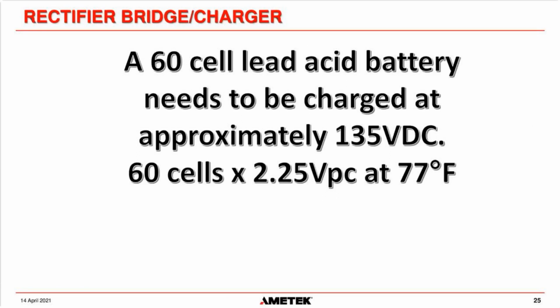That is really its only purpose, to keep your batteries charged. So if you lose power, your DC circuits will remain powered from the battery. And the thing about batteries is they are very sensitive to charge voltage. So a 60-cell lead acid battery needs to be charged at approximately 135 volts DC, which is 60 cells times 2.25 volts per cell at 77 degrees Fahrenheit. This is basically an approximate assumption. You have to look at your battery data sheet to make sure that the float voltage is what you think it should be. Some manufacturers like to see 2.23 volts per cell, some like to see 2.27 volts per cell, and sometimes they are quoted at 20 degrees Celsius. You've got to be careful about all these things.